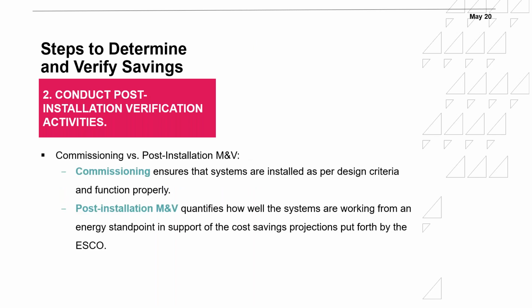So here's the difference between commissioning and post-installation M&V. Commissioning ensures that systems are installed as per design criteria and function properly. Post-installation M&V quantifies how well the systems are working from an energy standpoint in support of the cost savings projections put forth by the ESCO or the energy auditor. So these are the differences between the commissioning and the post-installation M&V. In the post-installation M&V, we're looking mainly at the energy consumption, making sure we are getting the savings or not.